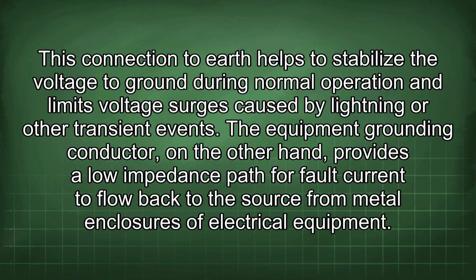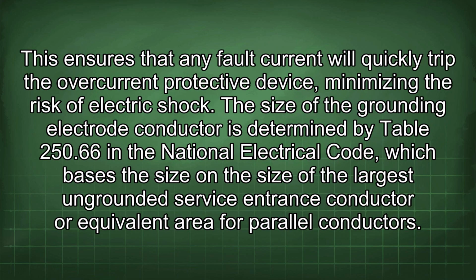This connection to earth helps to stabilize the voltage to ground during normal operation and limits voltage surges caused by lightning or other transient events. The equipment grounding conductor, on the other hand, provides a low impedance path for fault current to flow back to the source from metal enclosures of electrical equipment. This ensures that any fault current will quickly trip the overcurrent protective device, minimizing the risk of electric shock.